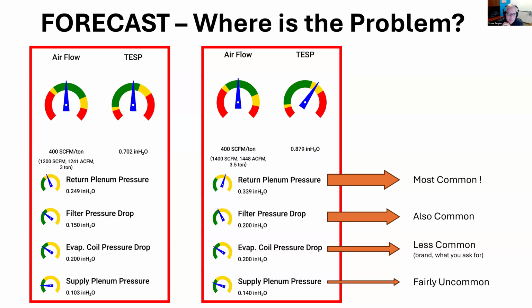And then supply plenum pressures being too high are fairly uncommon. That's not usually where the bottleneck is. It might be the bottleneck to one room, like maybe you've got one room that has a 6-inch branch and it needs an 8-inch branch. But that's relatively uncommon. It's usually the other 3 where the restriction lies. But the good thing is if you do the test with the TrueFlow, it will point you in the right direction to find out where is the problem and what can I do about it.